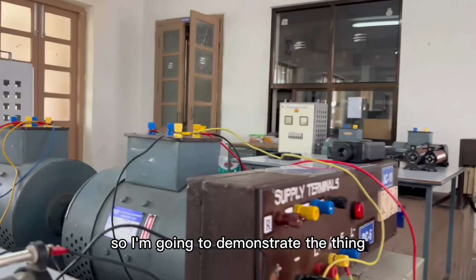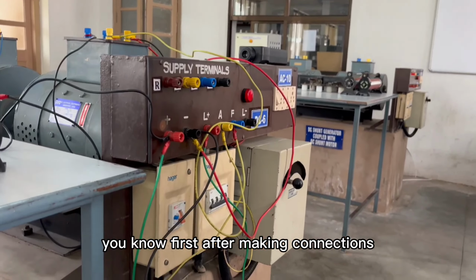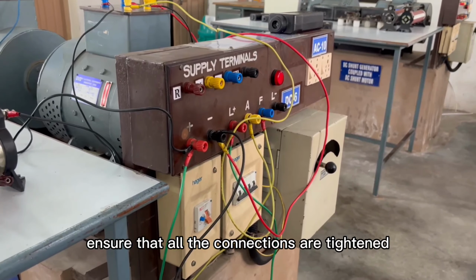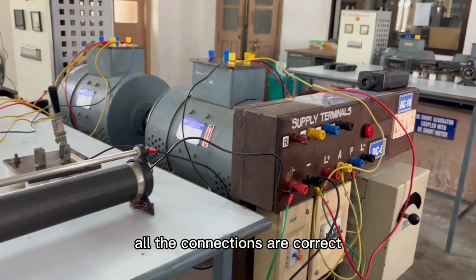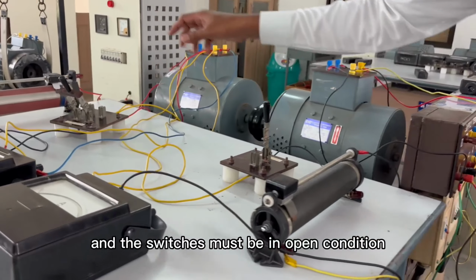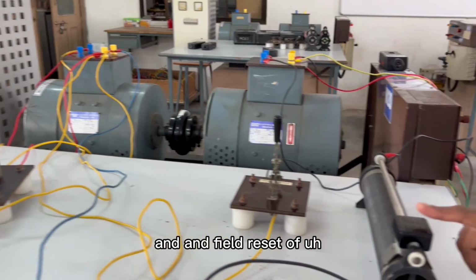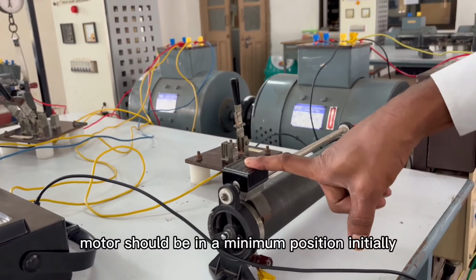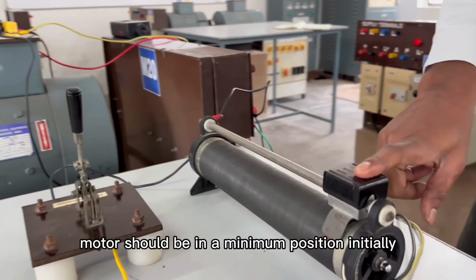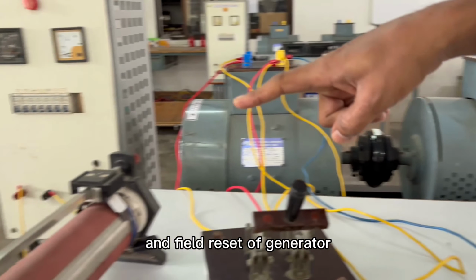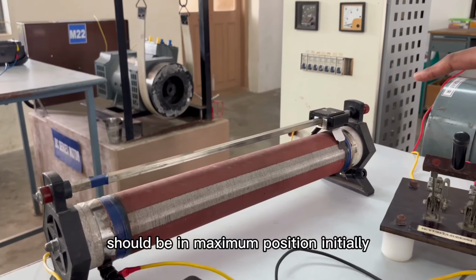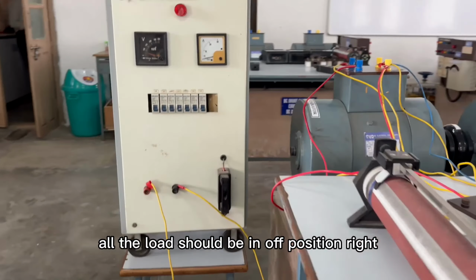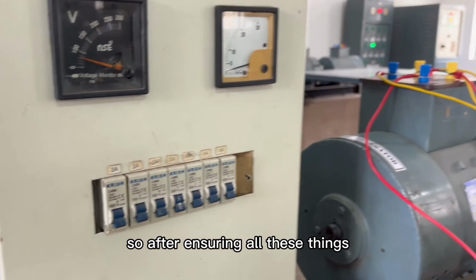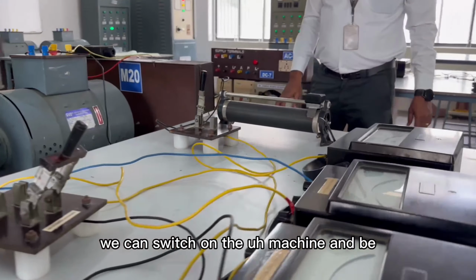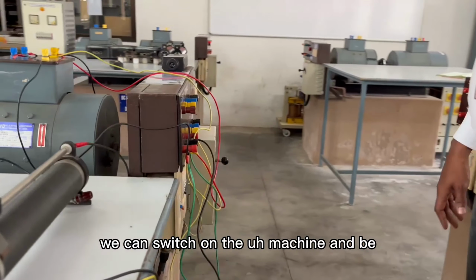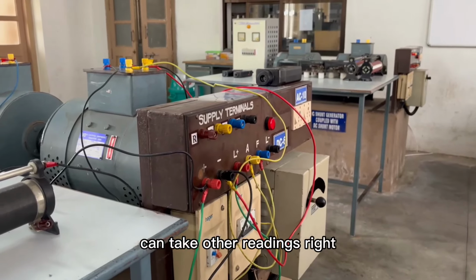So now I'm going to demonstrate the thing. First, after making connections, ensure that all the connections are tightened, all the connections are correct, and the switches must be in open condition. The field rheostat of the motor should be in the minimum position initially, and the field rheostat of the generator should be in the maximum position initially. All the loads should be in off position, right? So after ensuring all these things, we can switch on the machine, and we can take the readings, right?